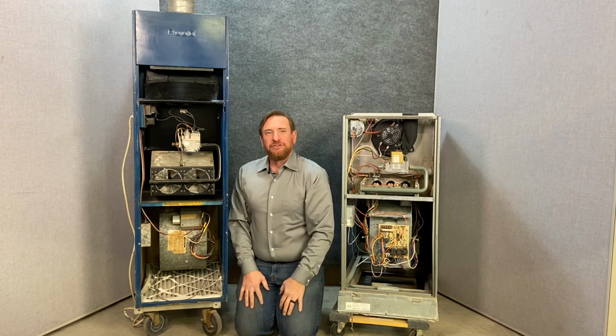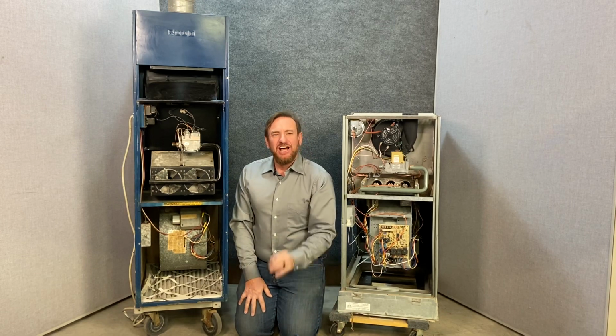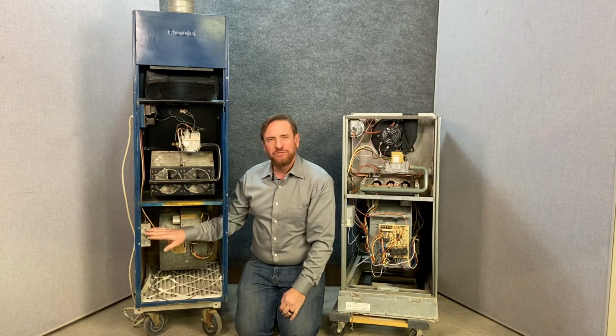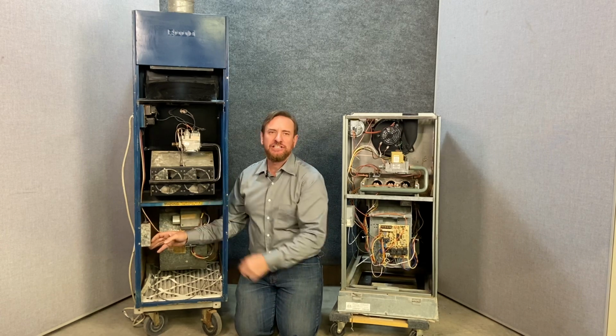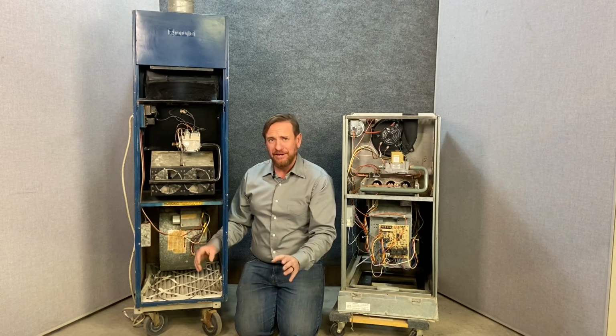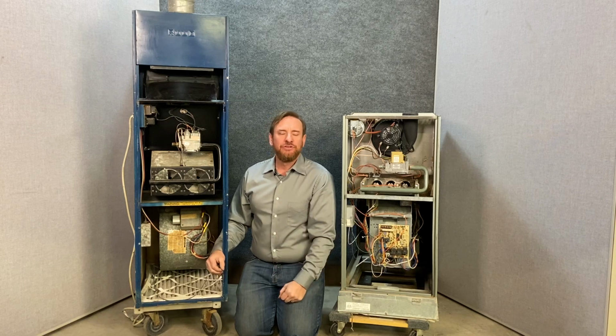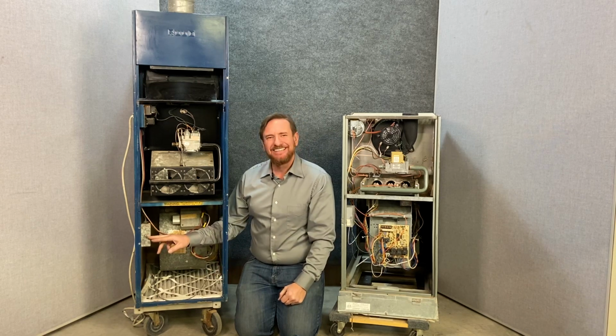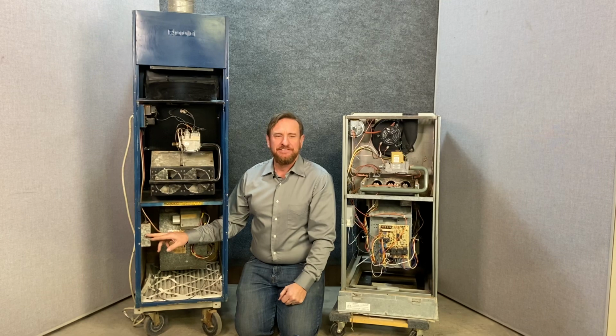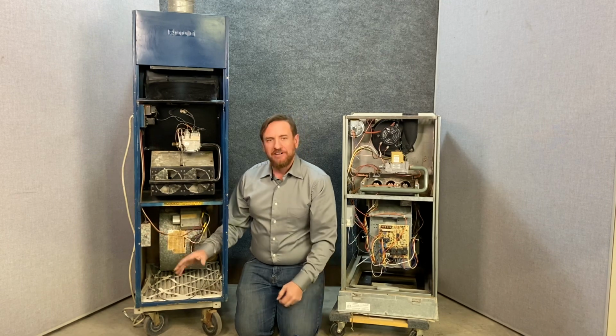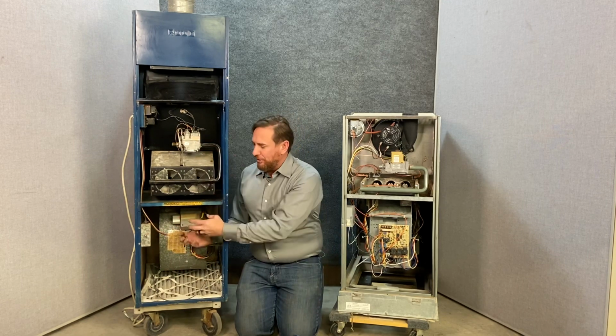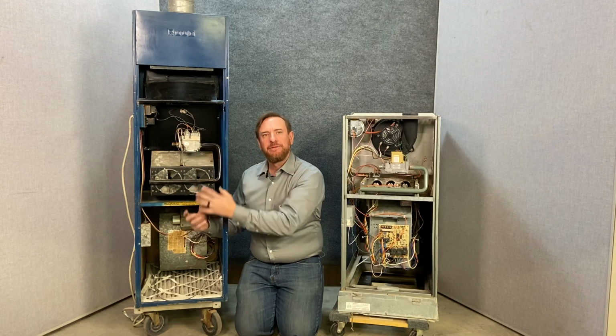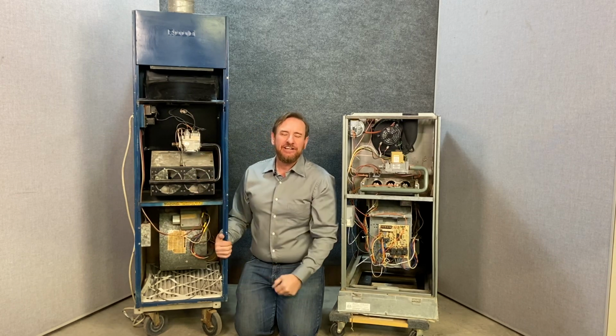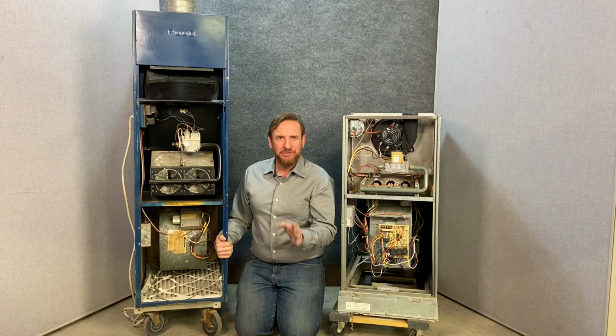That's really important for you to understand, because as a technician, you'll see a lot of people want to tape these switches to leave that on so they can check the whole system while it's working temporarily. The problem is, I've seen over and over again, people forget to take that tape back off, and that causes a safety hazard. Now the door may fall off, not get on there correctly. Now the blower is pulling the combustion air from the burner section into the house, and that could cause a carbon monoxide poisoning effect, and we don't want that to happen.